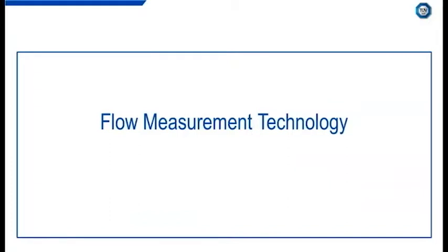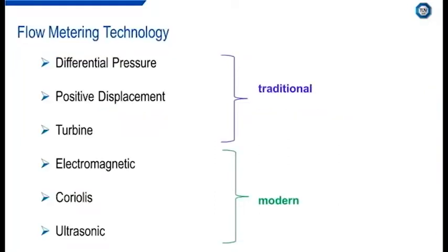So we have now covered the fundamentals of flow measurement. We can now look at some specific examples of flow measurement technology. There are many types of flow metering technologies available for a range of different applications. We have separated the flow metering technology into two categories that we will cover and discuss today, being traditional flow measurement technologies, such as differential pressure meters, positive displacement meters, and turbine meters. And I'll also cover some of the more modern technologies now available, including the Electromagnetic Meter, the Coriolis Meter, and the Ultrasonic Meter.